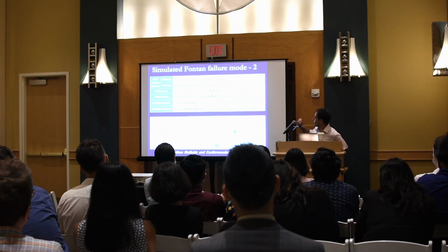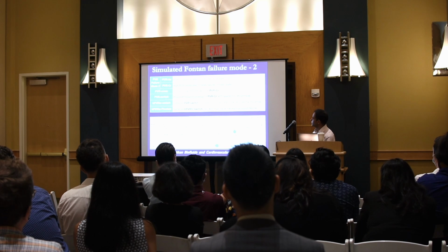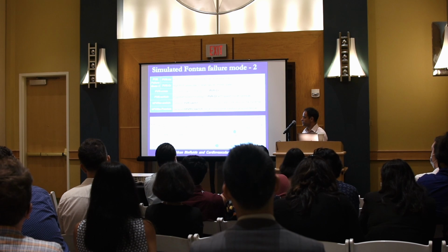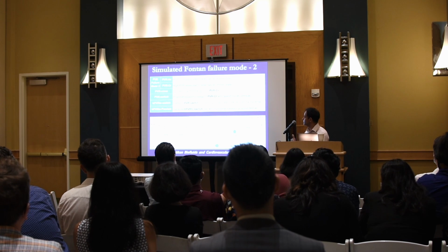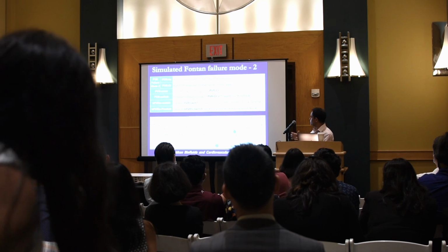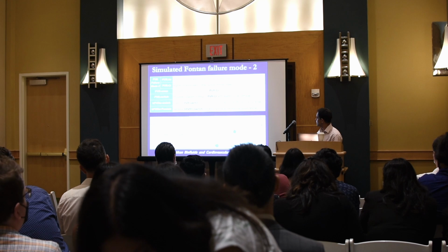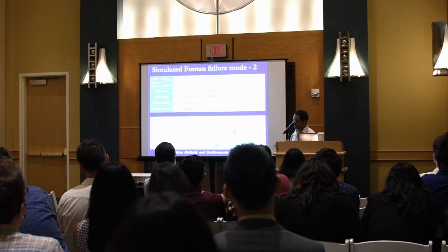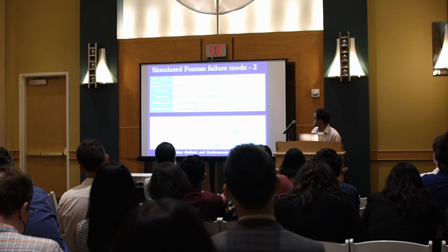Here we also wanted to test some very severe failure of the ventricle that has tachycardia and also bending of the outflow tract of the ventricle. So we have more severe versions of the failure mode.